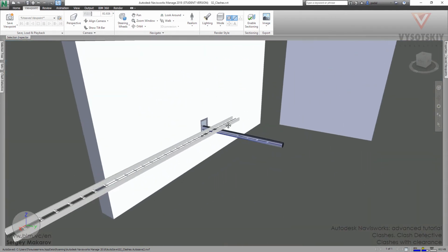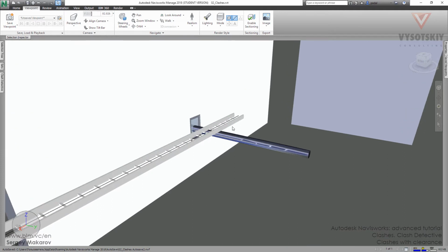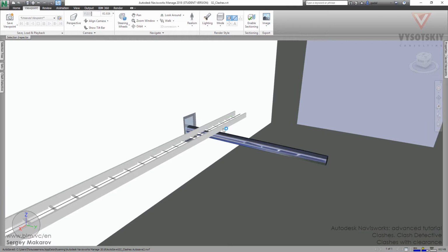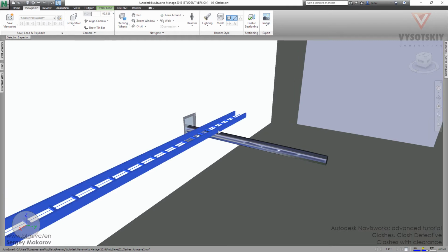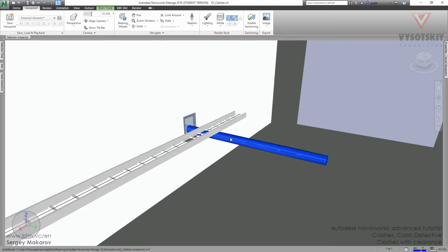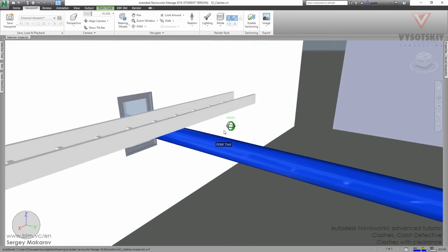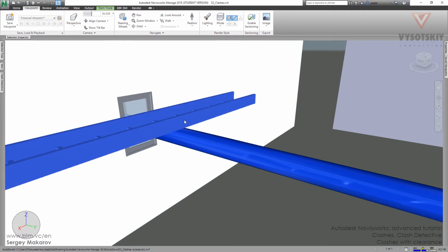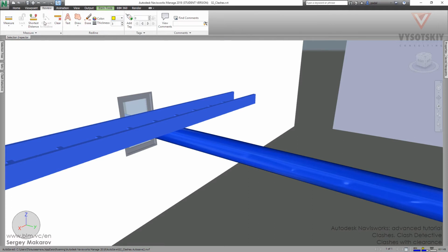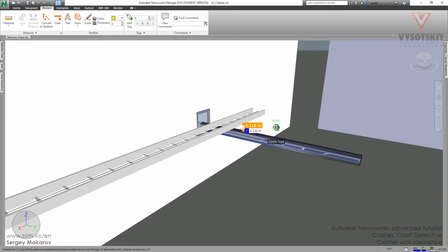And in Navisworks, we can find all the clashes between elements with clearance. So you can find all the cable trays which are located less than 15 centimeters from the pipes, if you have such a purpose. Of course, you can find all situations where you have a pipe near the cable tray, pick the mouse, then go to the Review button and press Shortest Distance and check it manually. But it's not the best workflow. Let's do it with Navisworks.